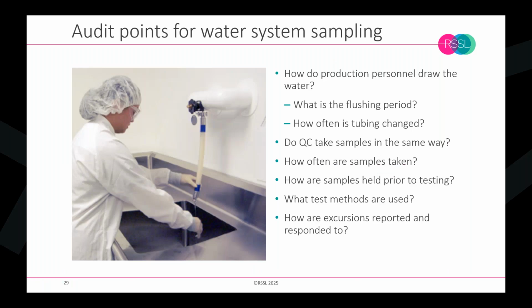It is also useful to conduct audits of the process of sampling, to follow the QC staff around, and then also to relate that to how production use the water. So if QC are flushing for 1 minute, but the production staff are flushing for a shorter time or not flushing at all, then the QC sample is not representative of the quality of the water that production are using. And then it's also important to understand the sampling plan: how often a sample is taken, what's the frequency, once samples are taken, what's the time limit on them being tested, and under what conditions do they need to be stored, are the test methods appropriate and validated, and then also to look at how water system excursions are dealt with. What's the procedure? Does an outlet go into quarantine? What is the definition of a problematic trend?